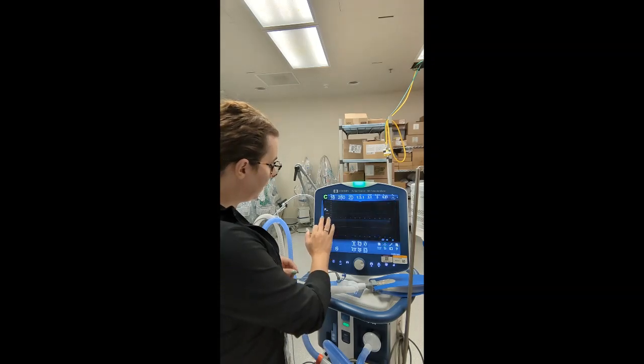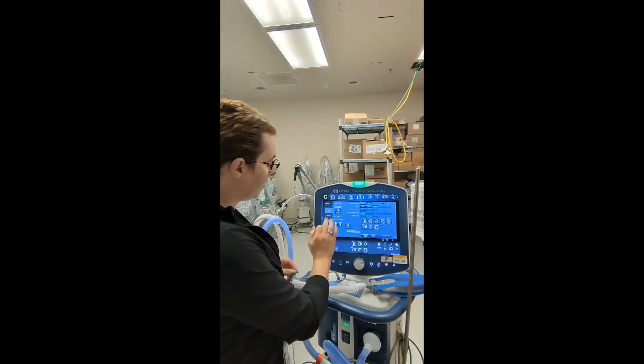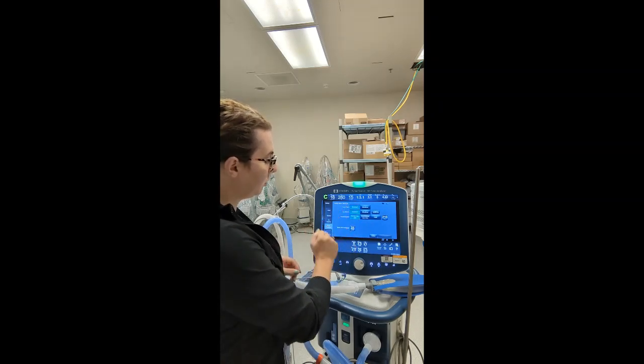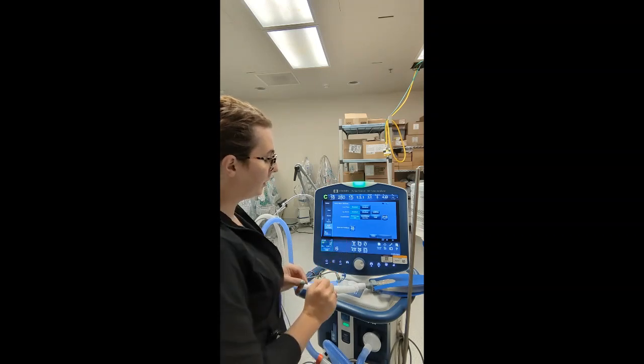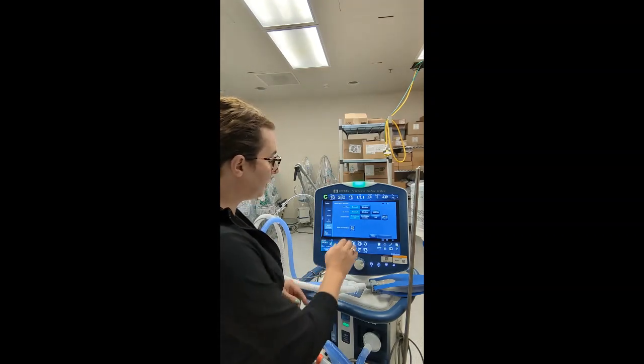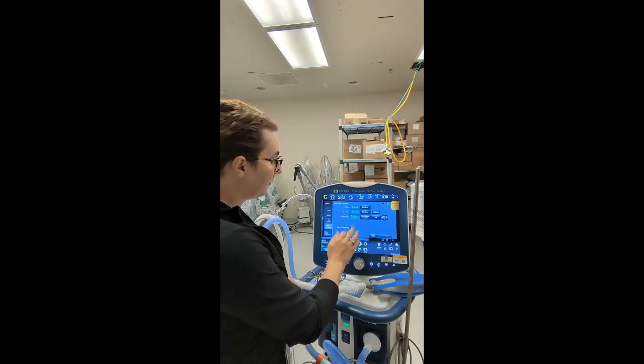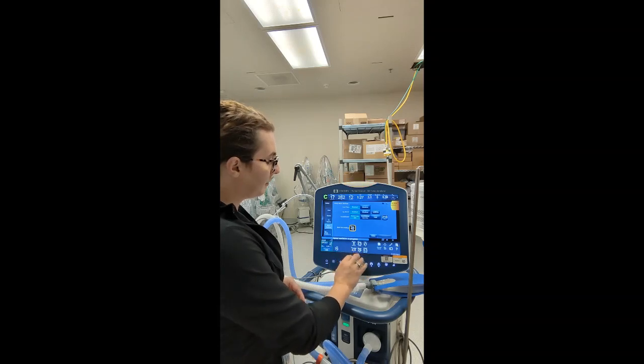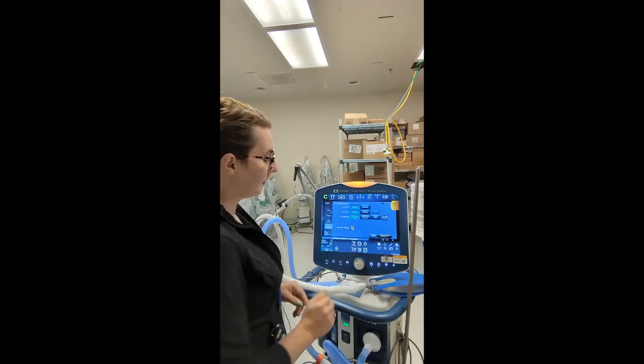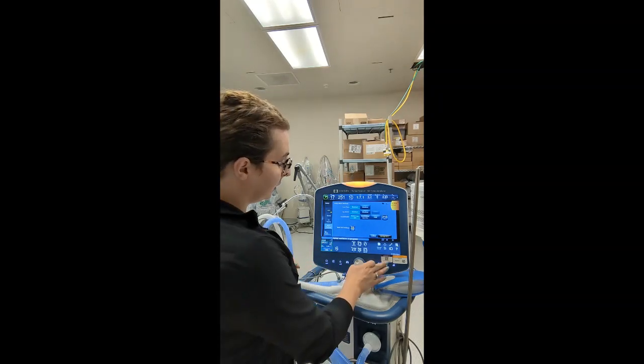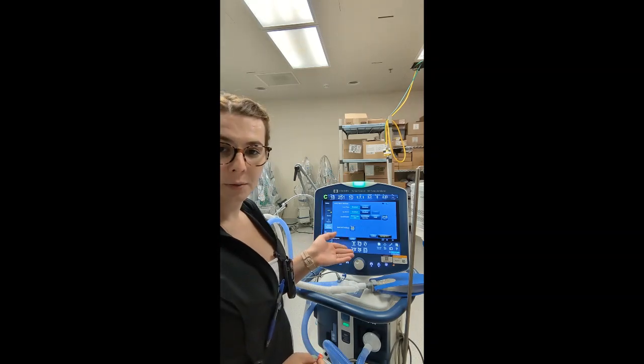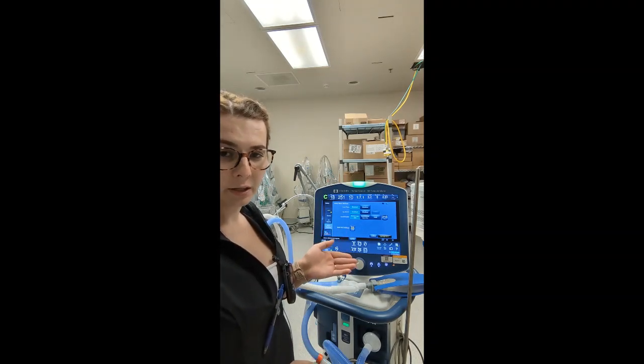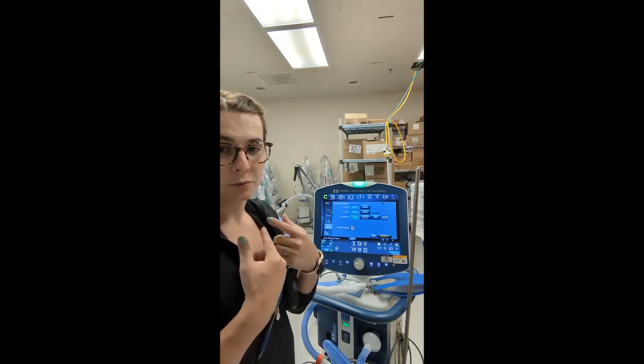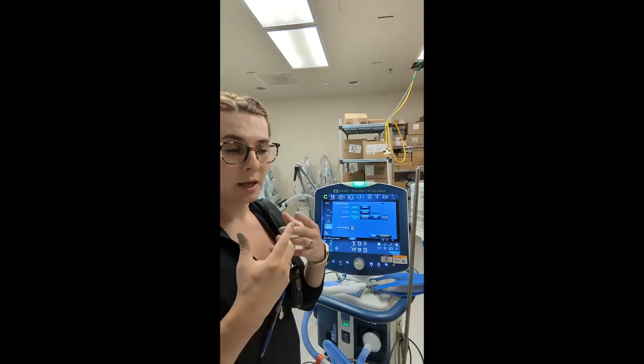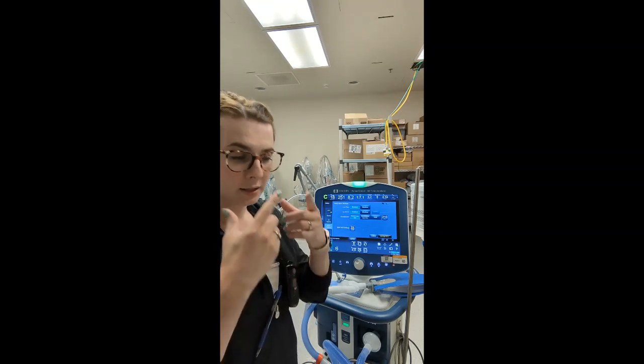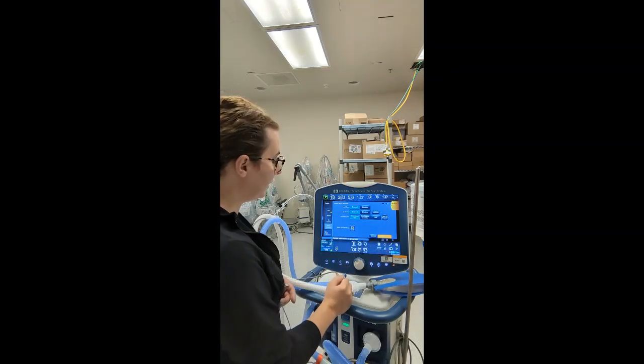And then we're going to go to more settings, and make sure our leak sync is enabled. We also want to increase our disconnect sensitivity. Default settings are 40 liters a minute. Now we want to increase that all the way up to 65 liters a minute. V60 is able to do 60 liters. With the Puritan Bennett, we can go all the way up to 65. This is to compensate for the leak that we will most likely have around our mask, because as we know, it can be difficult to get a perfect seal. Even a leak of 10 or 20, which is really good, can still cause the alarms. So we have our leak sync on and our disconnect sensitivity set.